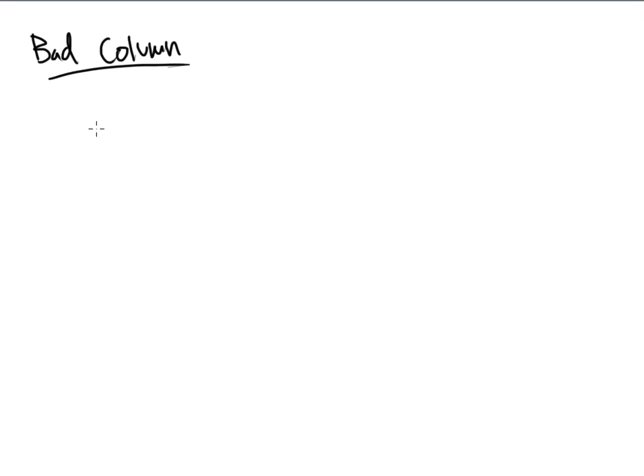And these bad columns, you'll know that you're going to get. They have very bad separations, or they'll start to show bad separations. If we were working in a regulated lab, our retention time shifts would not fly. But we kind of go with the flow. If we start to get a bad column, we just accept that fact and accept the new retention time and go on about our business. But sometimes that wouldn't work in a company, an environmental lab, or a pharmaceutical lab. They would say, absolutely not. We've got to figure out what the problem is.